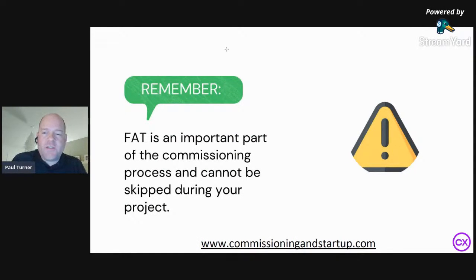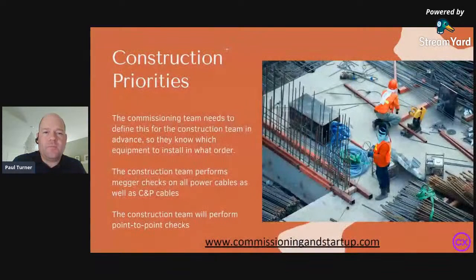So again, to stress that commissioning spans the length of the project, with the factory acceptance test being a very important part of that sequence. Upfront, the project leaders need to plan the proper integration of the hardware and software during the FAT. That means the software design is going to have to be ready a lot earlier, but it mitigates many possible impacts of cost and schedule by planning out your project that way.